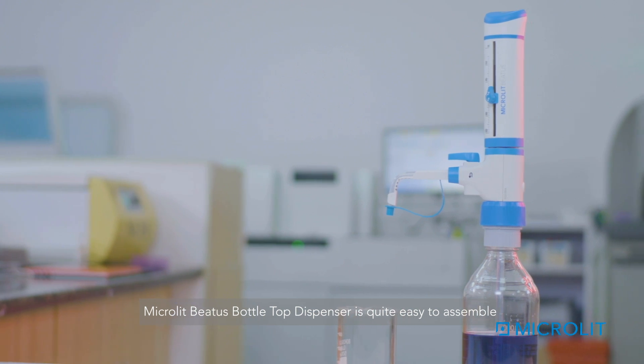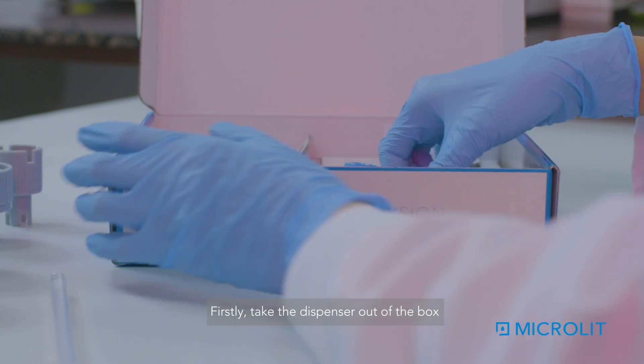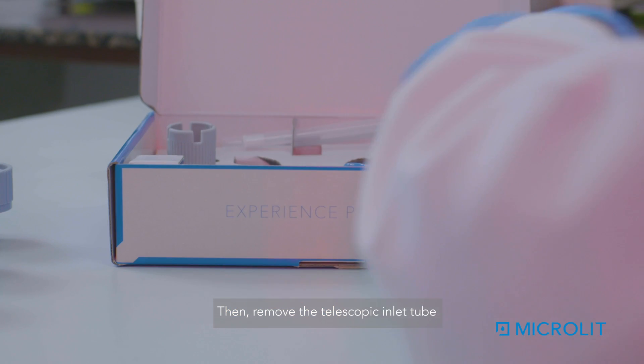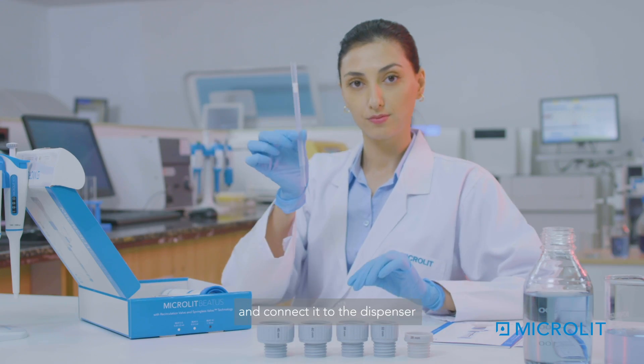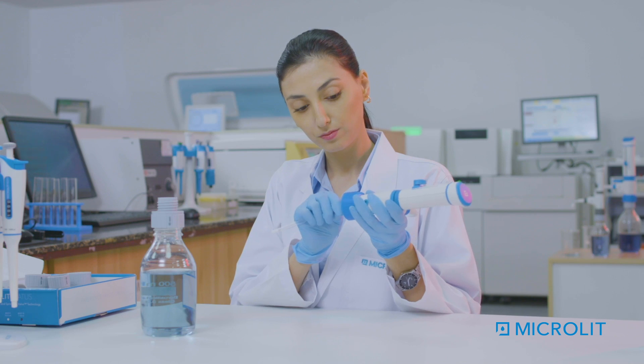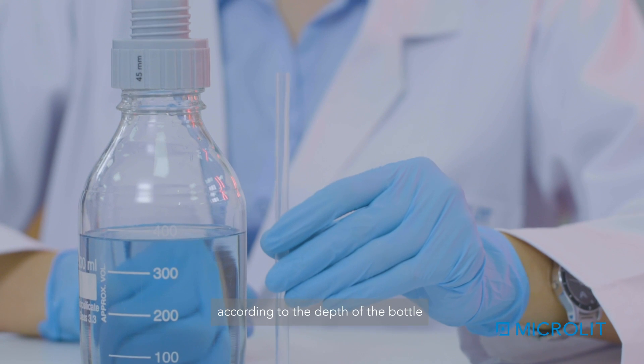Microlit Beatus Bottle Top Dispenser is quite easy to assemble. Firstly, take the dispenser out of the box. Then, remove the telescopic inlet tube and connect it to the dispenser. Adjust the length of the telescopic inlet tube according to the depth of the bottle.